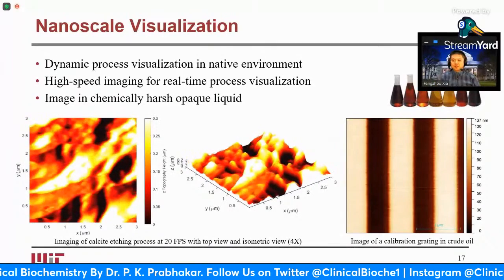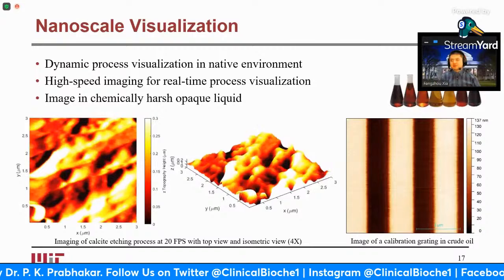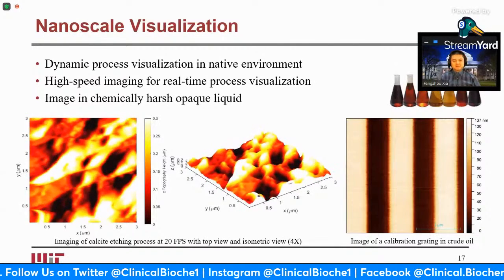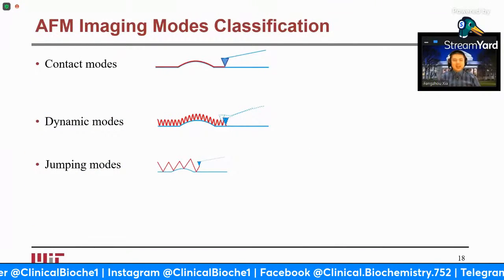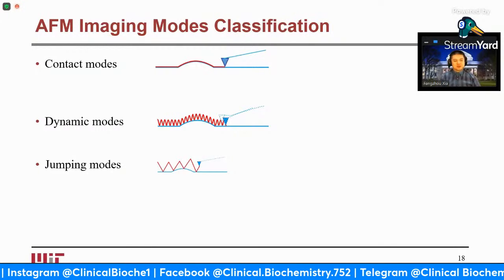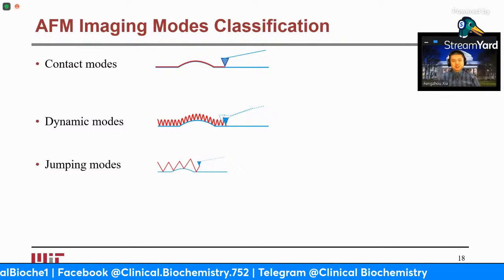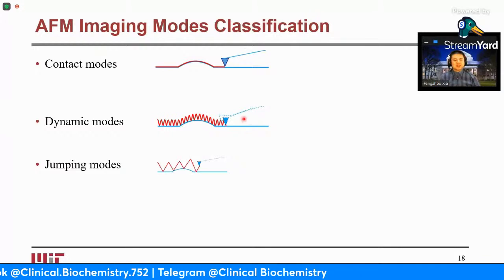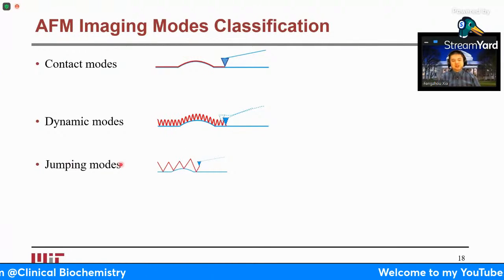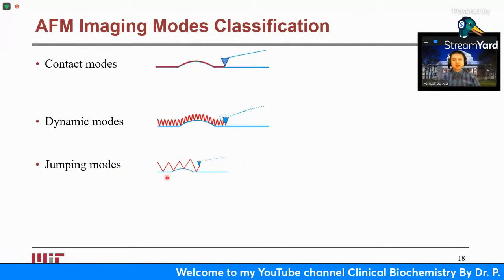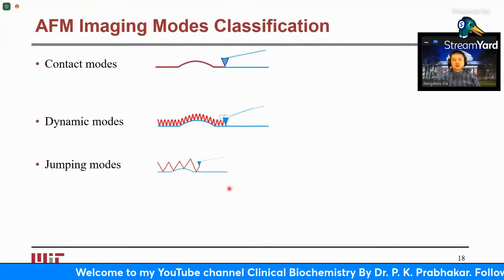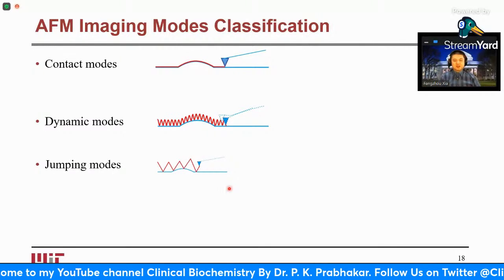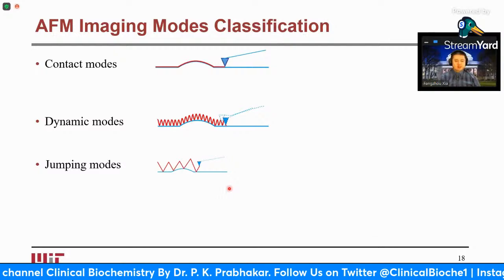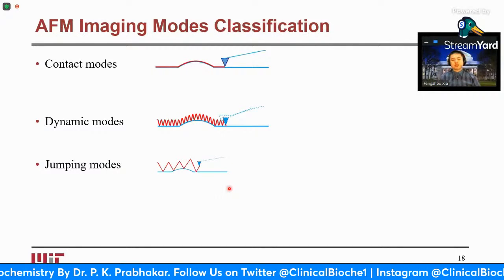Okay. Now let's move a little bit more into an outlook about the imaging modalities and what we can enable with AFM. On a general high level, we want to classify AFM imaging modes into 3 categories. One we call contact modes, where we always make contact between the probe and the sample. Then we have dynamic modes, where the resonance is excited. And then we have something called the jumping modes, where the probe and the sample make intermittent contact, and the resonance of the cantilever is not deliberately excited. This is typical if you're using Bruker AFM with their PeakForce Tapping, although they have a tapping mode, but it is usually doing this jumping mode.